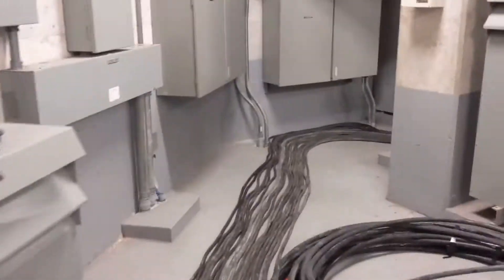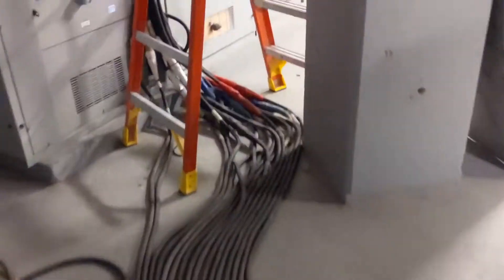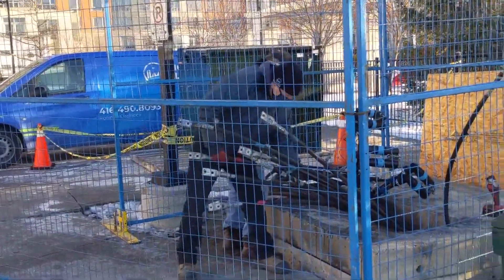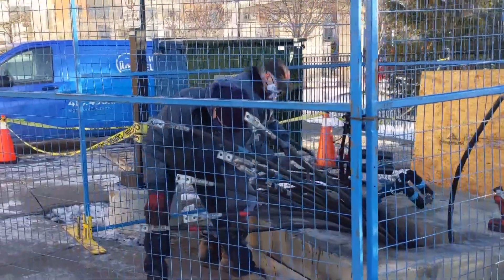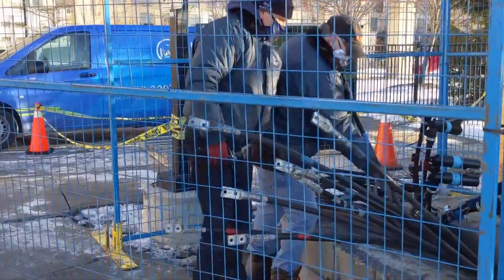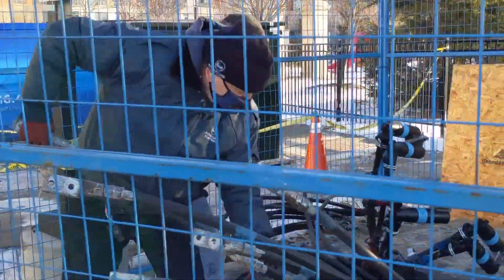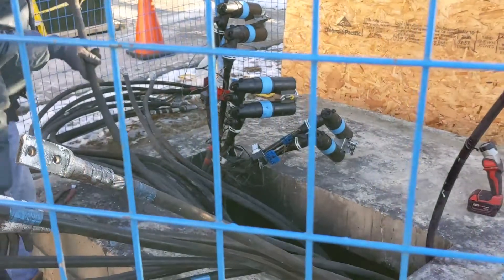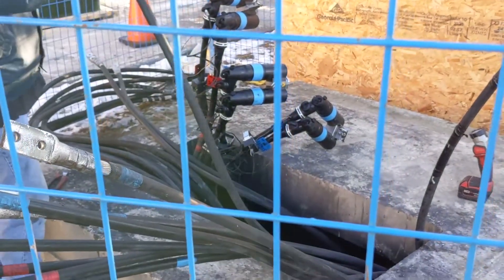The guys came back and started testing the cables. I'll show you downstairs — some of the cables were literally burnt inside the ducts. There's a set of ducts that bring these cables back into the building and into the electrical room underground, and we found that several of these cables are damaged. They're burnt right through. That's the reason the transformer burnt out.